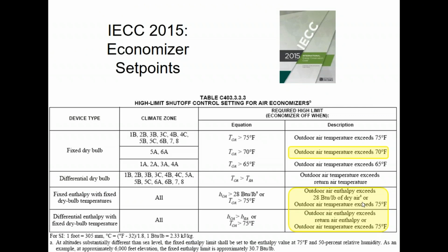If you have a dry bulb economizer, you're required to set up the control system to do the changeover at a 70-degree set point. You can no longer use 55. You can no longer use 60. It has to be set for 70 degrees.